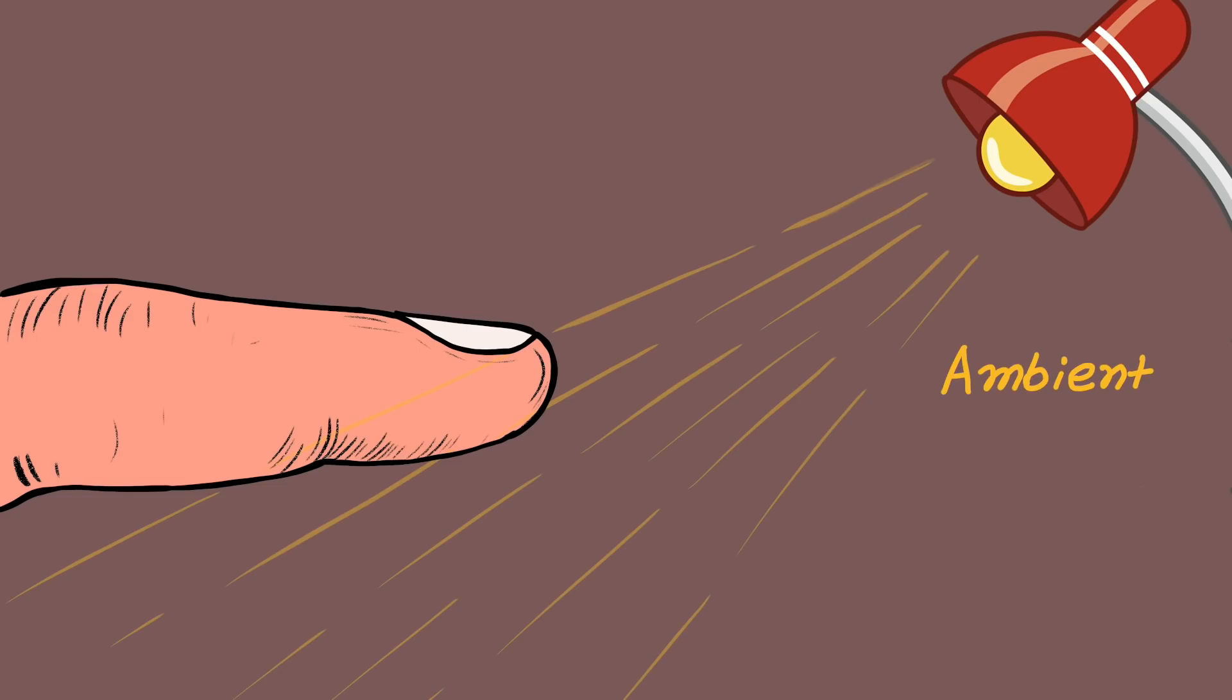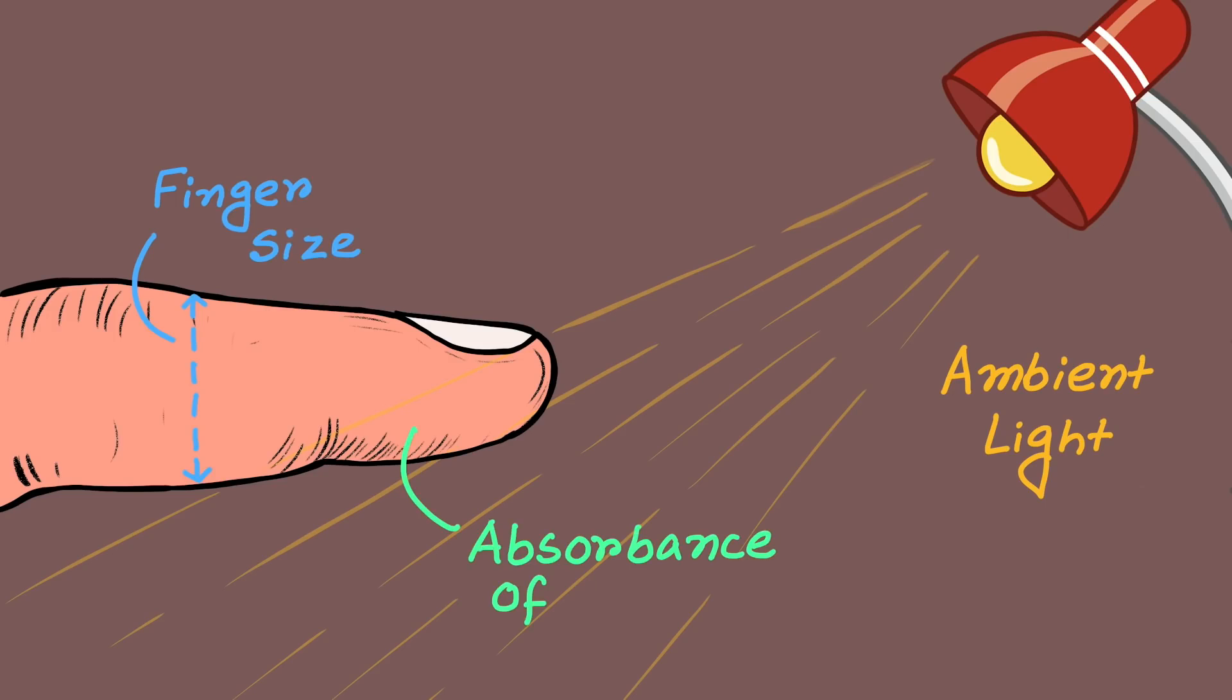The device has to compensate for the ambient light, finger size and the absorbance of the rest of the tissues. There is a reference curve saved in the memory of the device to calibrate the incoming readings and to normalize them.